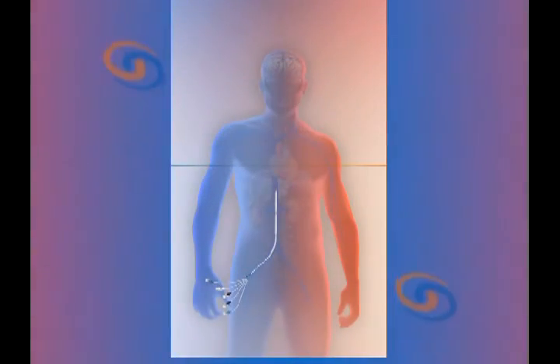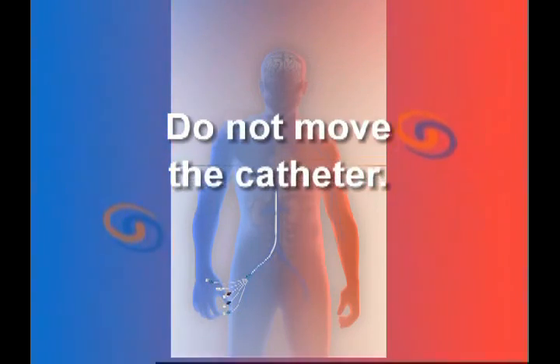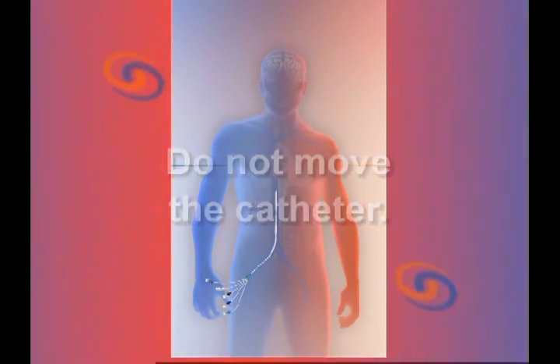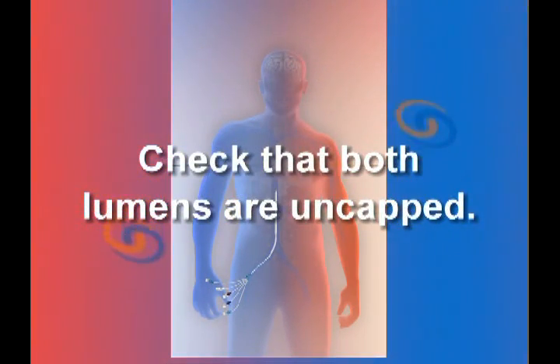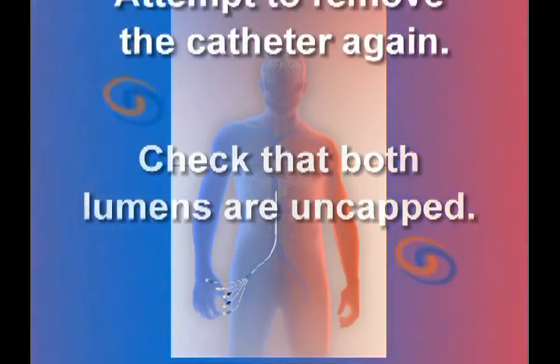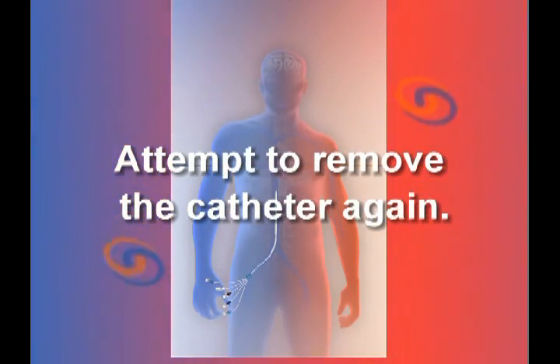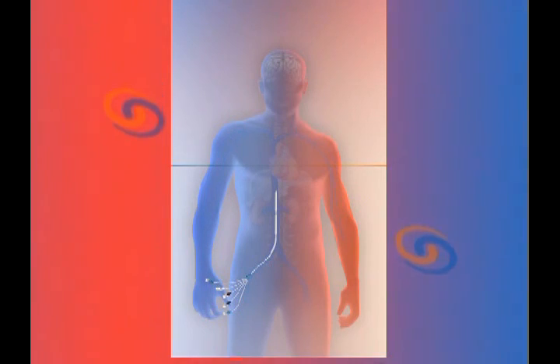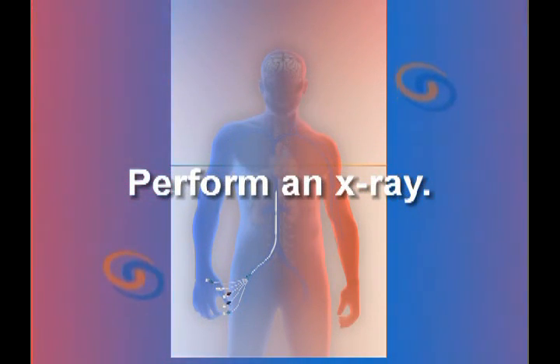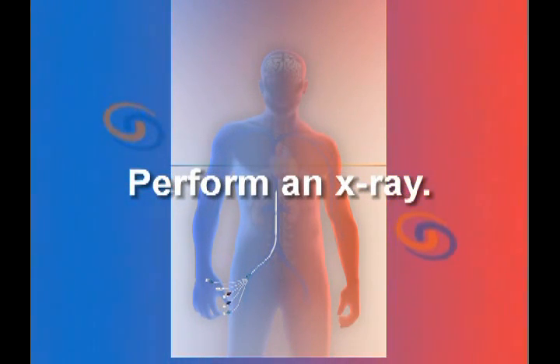If you feel any resistance during removal, do not move the catheter. Check that both the inflow and outflow lumens are uncapped. Attempt to remove the catheter again. If resistance is still encountered, perform an X-ray to determine the cause of the resistance.